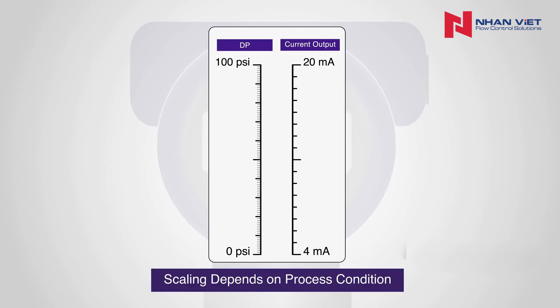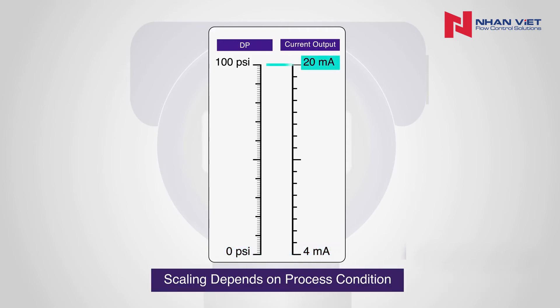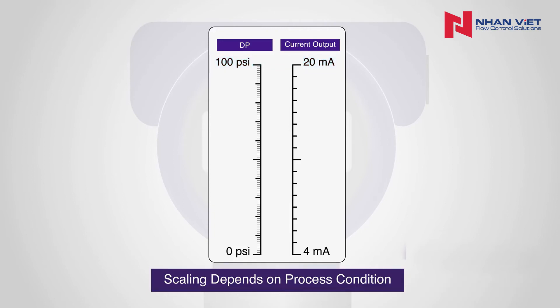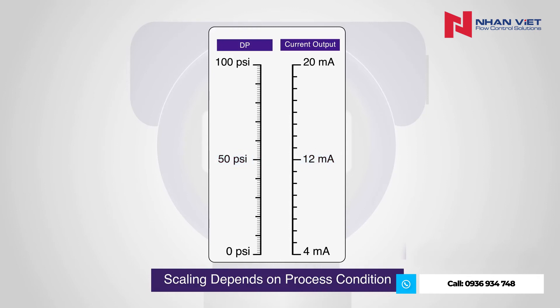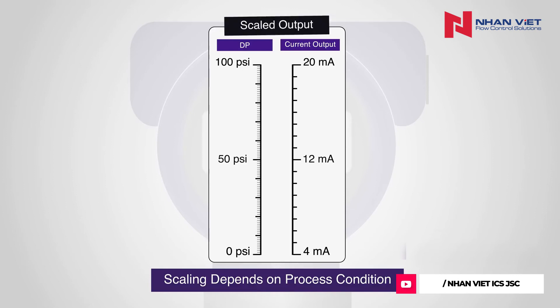The electrical output generated by the DP transmitter electronic module is linear and proportional to the actual measured delta P. Depending on the range of measured pressure, a 4 milliamp signal would equal a measured delta P of 0 psi, and a 20 milliamp signal would equal the maximum measurable value — in this case, 100 psi. Using these variables, we would know that a 12 milliamp signal would equal 50 psi delta P. The relationship of the produced electrical signal to the units of measure is called the scaled output.